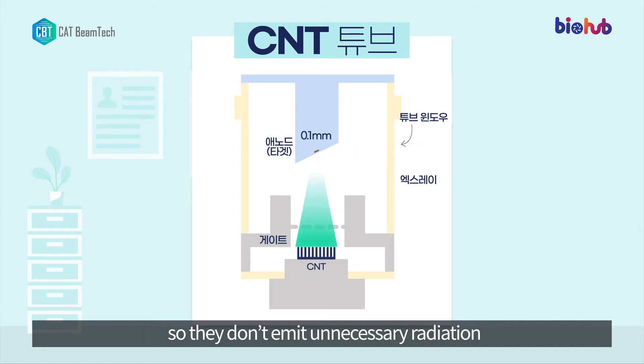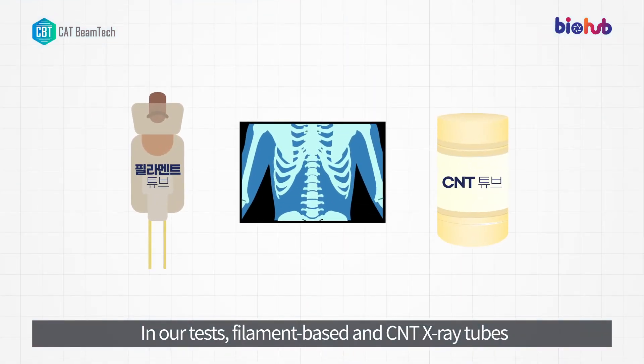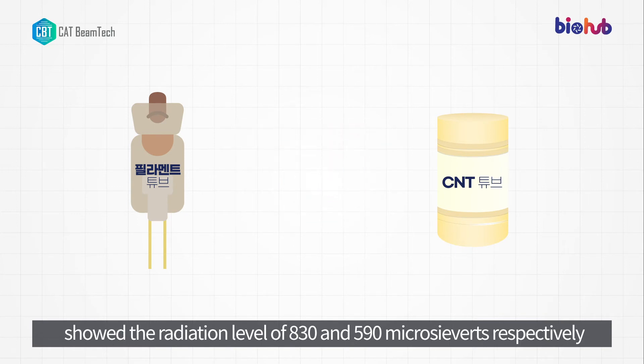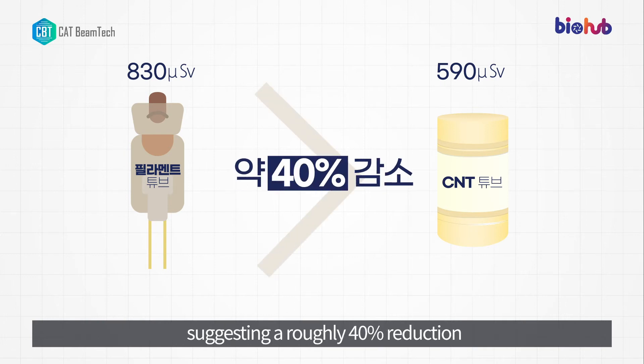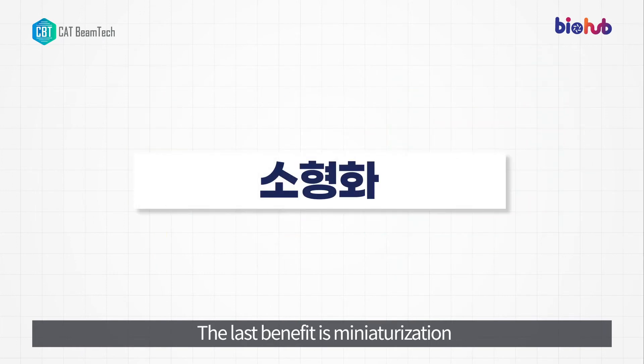So they don't emit unnecessary radiation. In our tests, filament-based and CNT X-ray tubes showed radiation levels of 830 and 590 microsieverts respectively, suggesting a roughly 40% reduction in radiation exposure with CNT X-ray tubes.